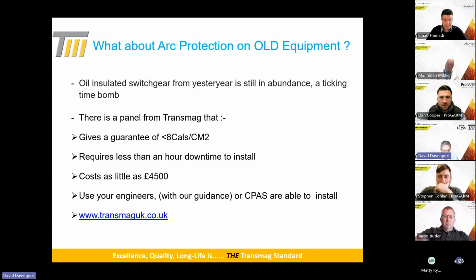One of our biggest threats at the moment - I'd say at least 1 in 3 switch rooms and substations I see - has oil insulated switchgear from yesteryear still in abundance, giving calories per centimetre squared way off the scale. Even category 4 arc flash PPE won't cover many installations done in yesteryear. That doesn't mean you shouldn't wear it just because the calorie level is above that - in fact it's an even better reason to wear it, because some protection is always better than no protection.